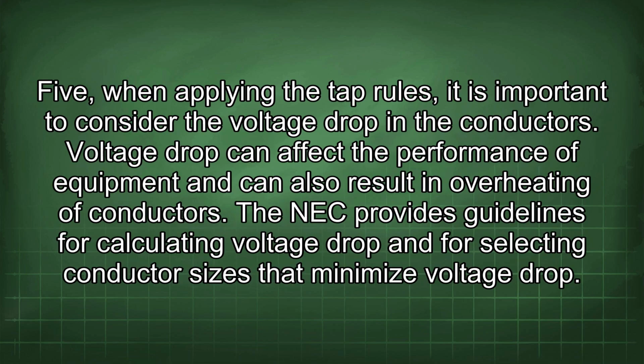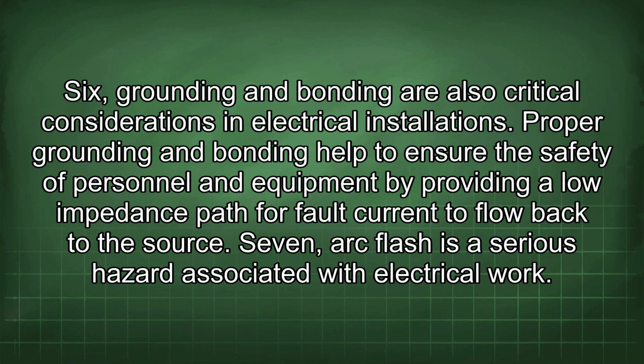5. When applying the tap rules, it is important to consider the voltage drop in the conductors. Voltage drop can affect the performance of equipment and can also result in overheating of conductors. The NEC provides guidelines for calculating voltage drop and for selecting conductor sizes that minimize voltage drop. 6. Grounding and bonding are also critical considerations in electrical installations. Proper grounding and bonding help to ensure the safety of personnel and equipment by providing a low impedance path for fault current to flow back to the source.